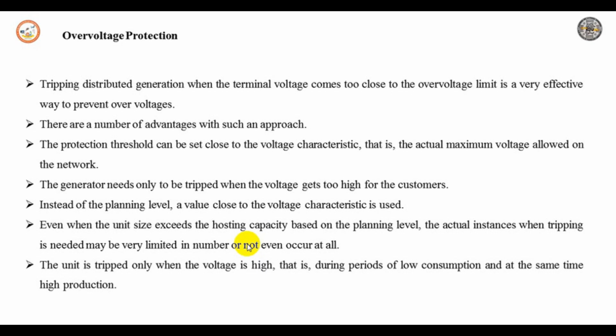The disconnection and reconnection can result in significant voltage steps where a large amount of generation is involved. A spread in the voltage threshold and a spread in the reconnection time could be used to make the transition smoother with a large penetration of solar power in the distribution network. So this will trip due to over voltage again, which becomes a common phenomenon. This would result in serious tripping, and could also happen around noon on every sunny day. So a reduction in the amount of energy generated this way is not a feasible solution. The curtailed energy would therefore be a much higher percentage than the percentage of time that is available to generate. So this is about over voltage protection and some of the techniques that are available for it.